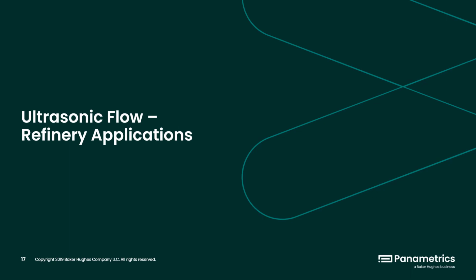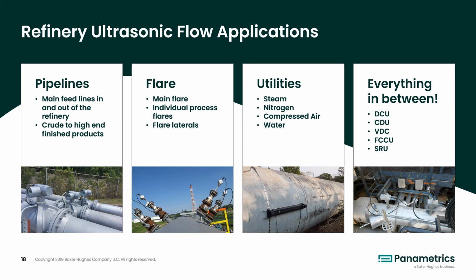With the understanding of how ultrasonic flow meters function and details on extreme temperature ultrasonic flow measurement, let's move on to some examples of how ultrasonic flow meters are used in refinery applications. Ultrasonic flow meters operate everywhere in refineries, from main feed lines in and out of a refinery, to exhaust flare lines which are required for balance of plant and emissions monitoring, to the utilities measurements which you might naturally think of, and then everything in between.